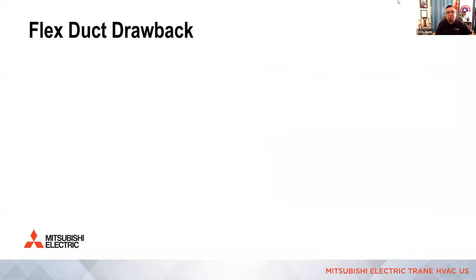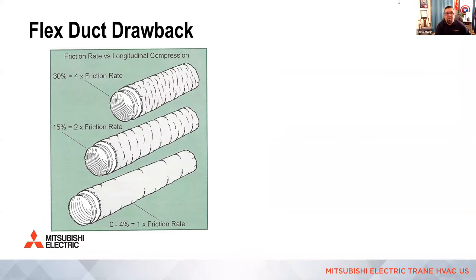All right, so there is some drawback with flex. I would say the number one drawback is what happens to friction rate, because people don't actually pull that helix on the inside taut. If you have less than 4% compression on a flexible duct, then you use the normal friction rate. Everybody, just so you know, this is for galvanized sheet metal. When you use a duct calculator, they do make ones for flex runs, and there's an adjustment for compression. Basically, with residential applications, the rule is you pull that helix straight and tight. And if you want to make any turns, you use hard 90s. You shouldn't be making turns with flexible duct.